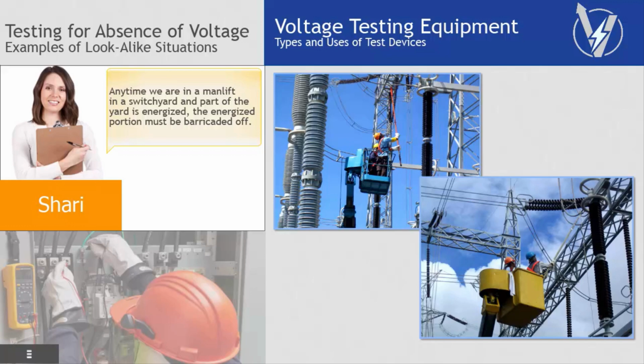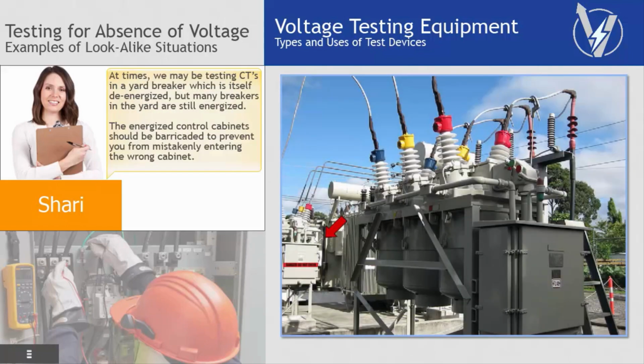Anytime we are in a man lift in a switchyard and part of the yard is energized, the energized portion must be barricaded off. At times, we may be testing CTs in a yard breaker which is itself de-energized, but many breakers in the yard are still energized. The energized control cabinets should be barricaded to prevent you from mistakenly entering the wrong cabinet.